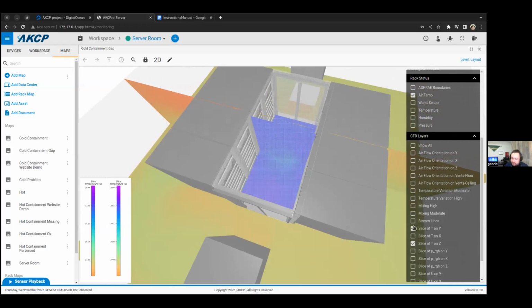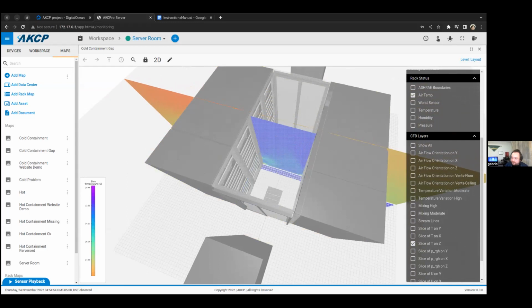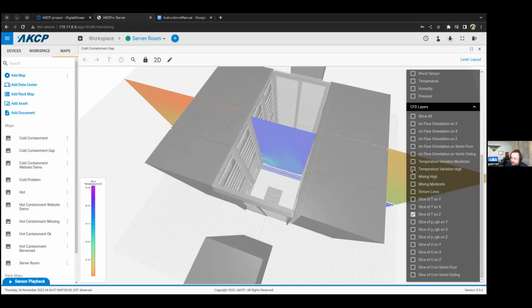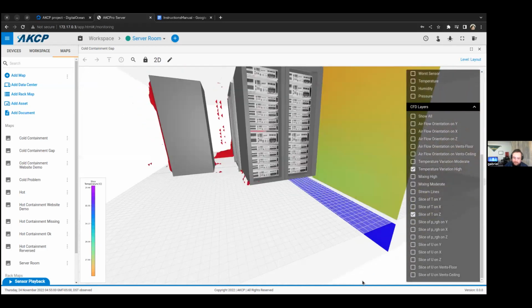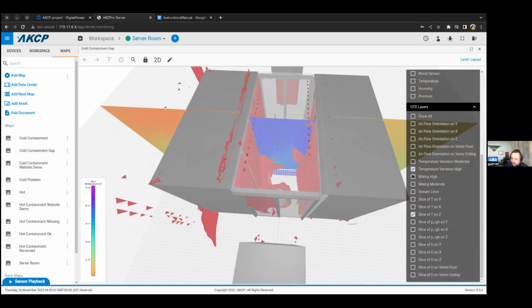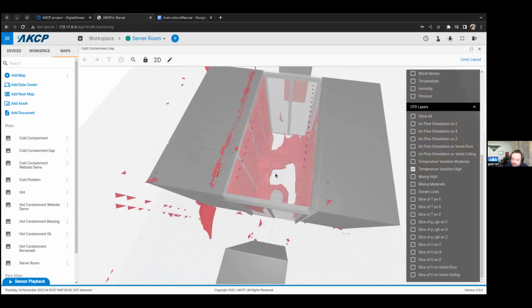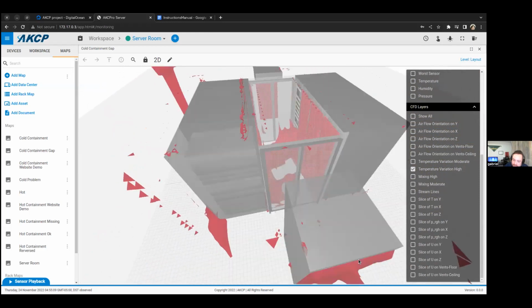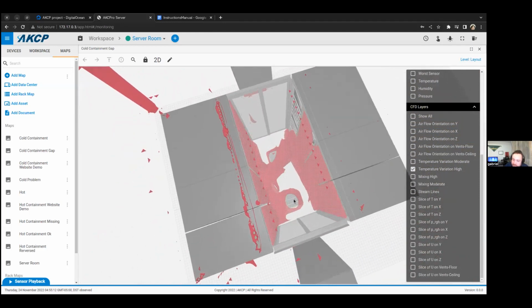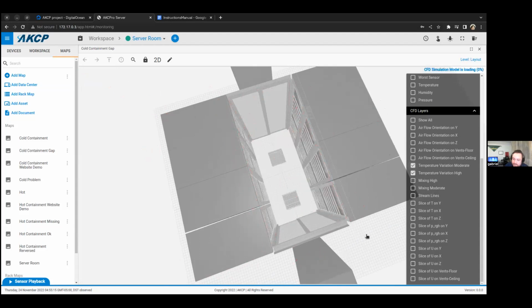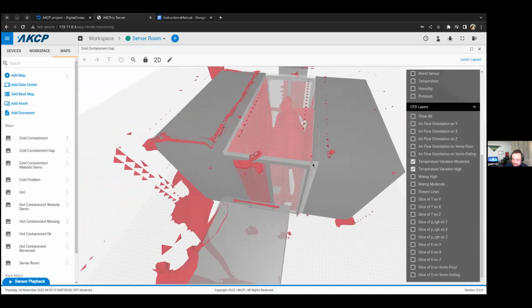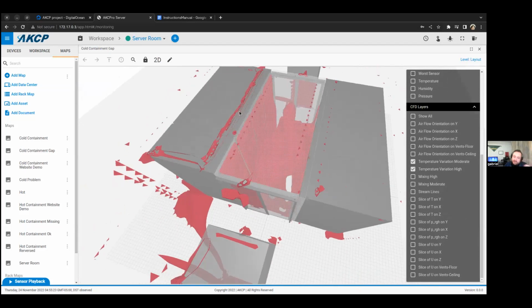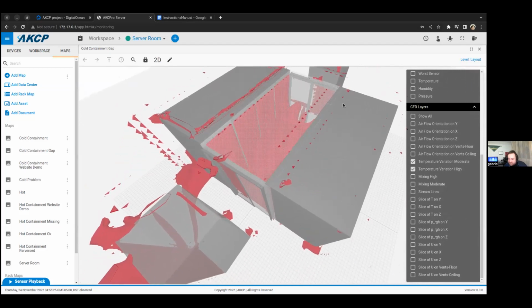But you don't have to search with the map like that. We already have a tool to see the mixing. We have that tool that shows the zone where you have a high temperature variation. So it will underline, or I just removed it, and show where you got the air mixing. If you got a great gradient, you can see it on the map. I can moderate to see a bit more. So we see that we got a lot of mixing. It's a numerical simulation, so you will always have a bit of noise like that.